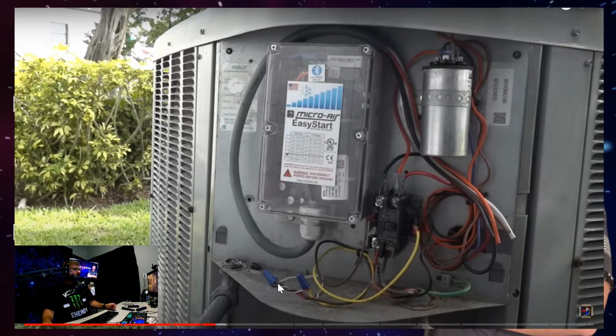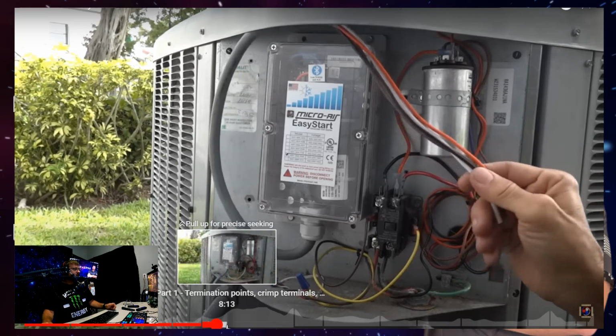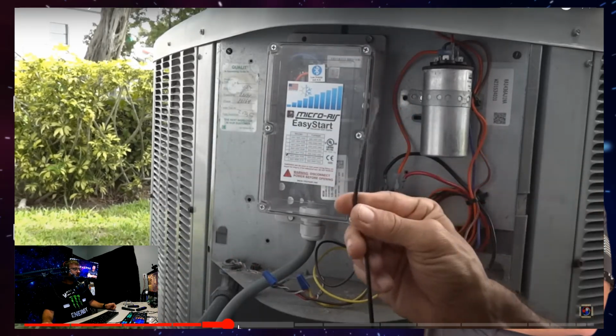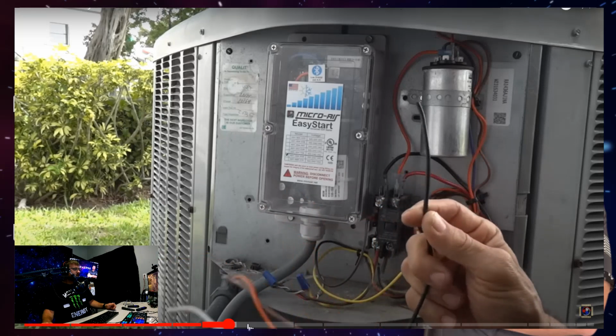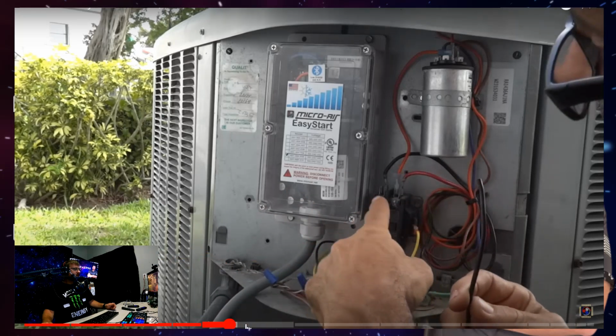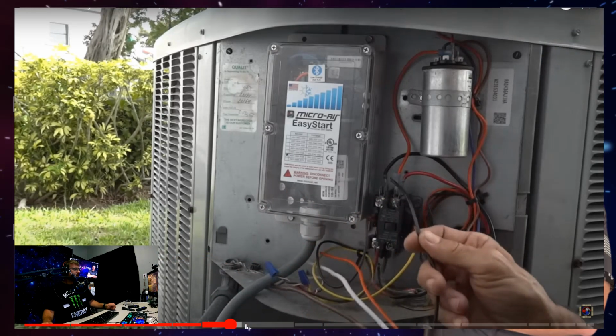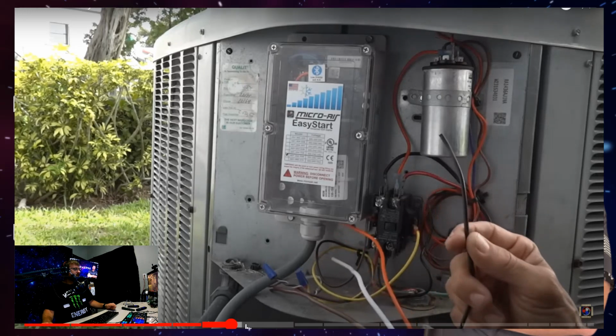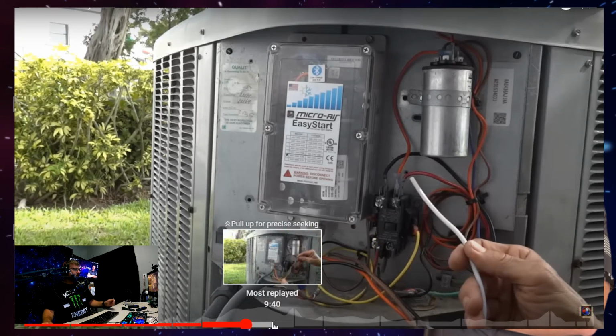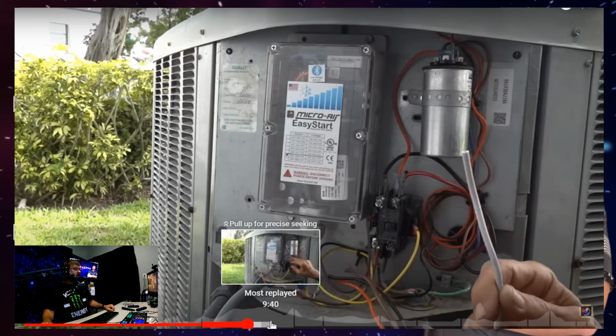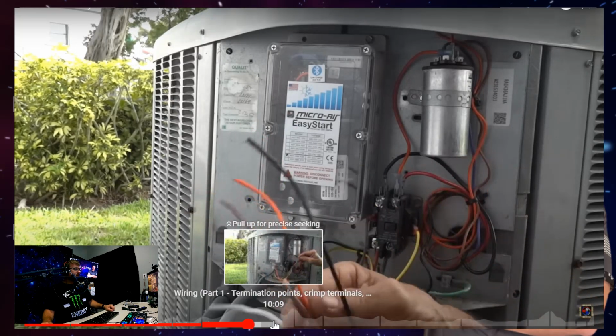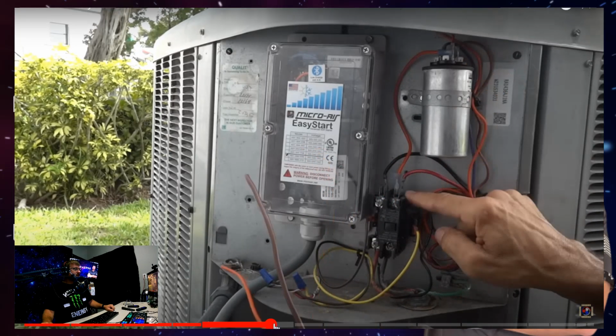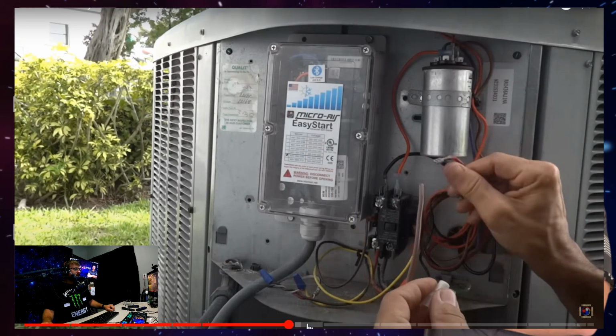We're ready to start the wiring now. And in this case, I've already cut back this harness. This black wire is going to go to the compressor common, which corresponds to the L1 pole on the contactor here, which also has a black wire. Connect the white wire to one of these available points. The third wire that we're going to connect is going to be up here on the run capacitor.